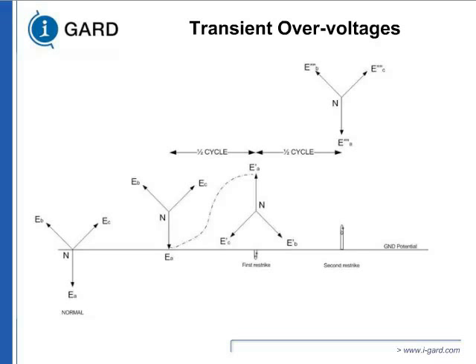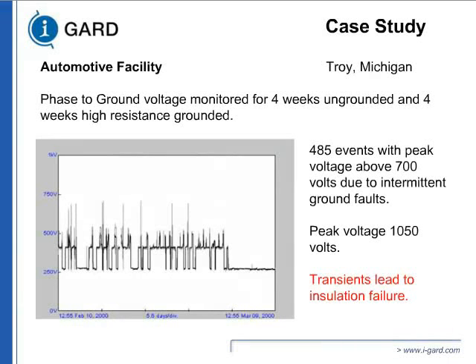This is a true example. You can see the actual measured waveforms from an automotive facility. Phase to ground voltage, ungrounded, and then we'll show you high resistance grounded. You can see the pulses. If you're familiar with the term high potential test, or high pot, that is what is happening to your system.